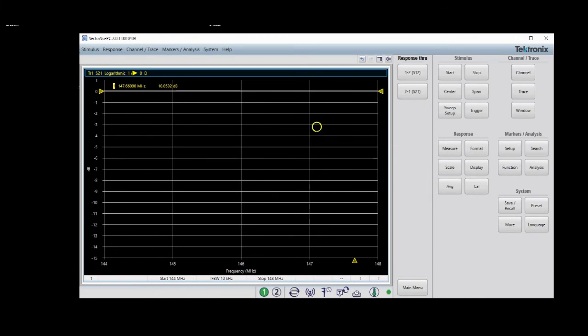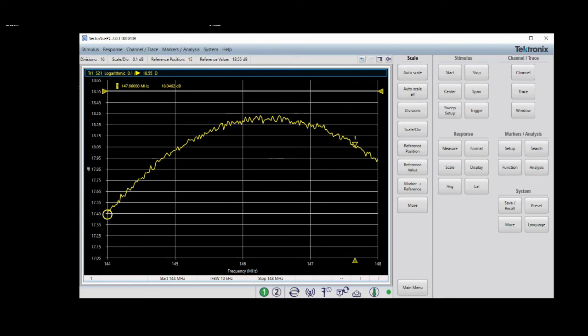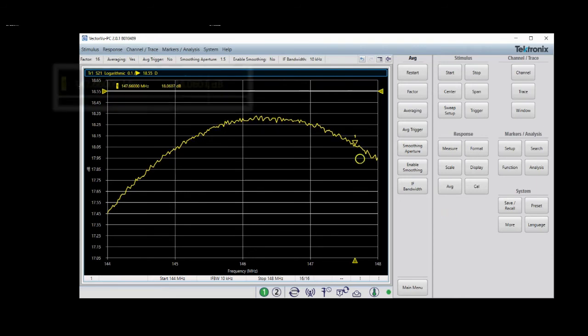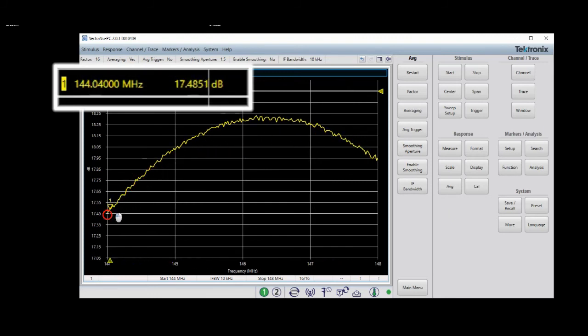The unit under test is now connected. We don't see anything on the screen because our scale is way off screen. So let's do an auto scale, bring it in. It's kind of googie, so let's average it to make it look nice and smooth. Now let's take a look at this data here. We have, at the low end, 17.45 dB of gain. Our maximum gain is somewhere up in here at only 18.3 dB.